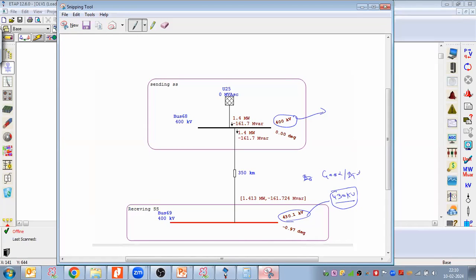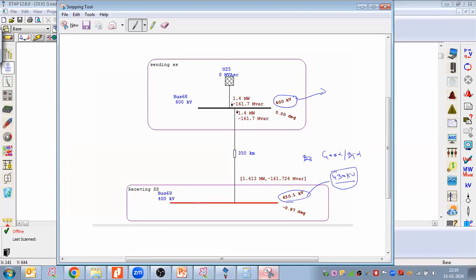Why is it bad? Because your system is designed for 400 kV only, right? All your equipment, breaker, CTVT, transformer, each and everything, you have designed for the 400 kV rated voltage. But at the same time, you are feeding those equipment 430 kV. It means the equipment insulation may get damaged due to higher voltage stress. So it is bad, right?